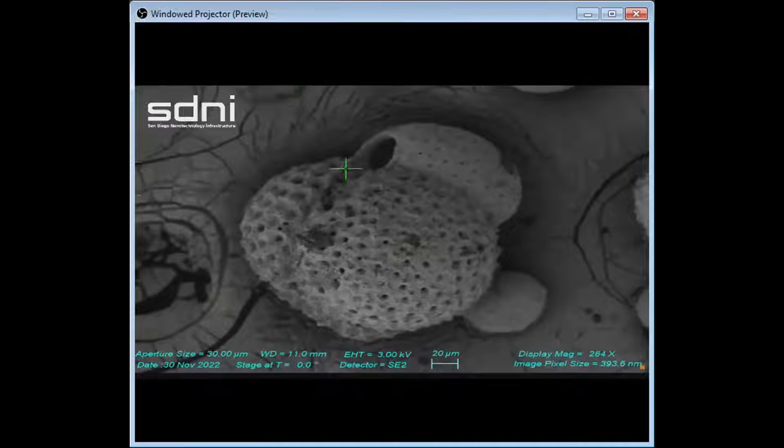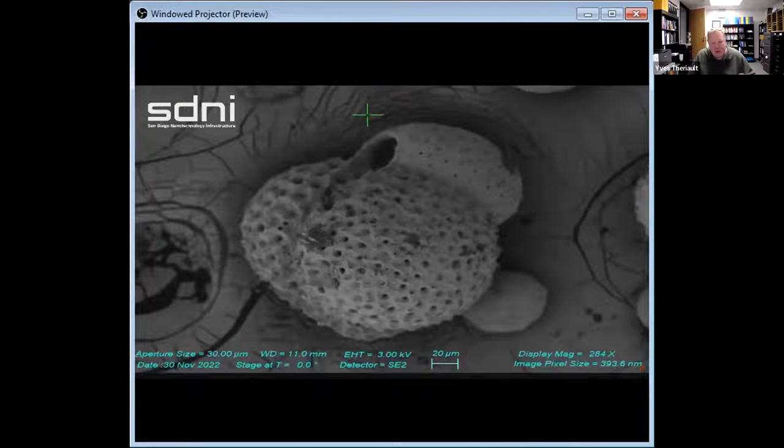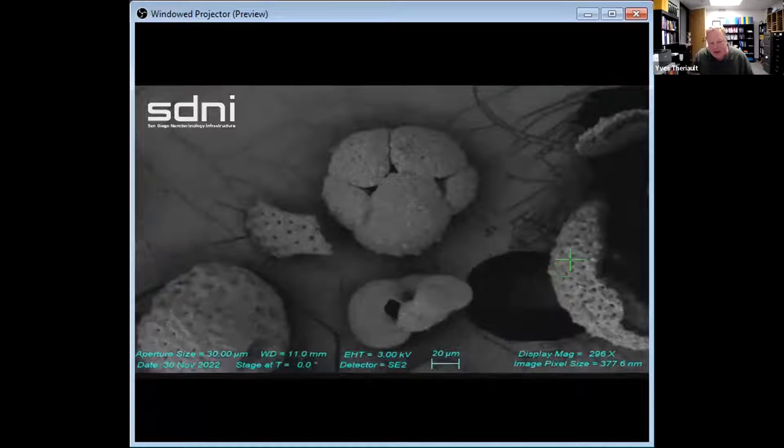When you guys are operating the SEM, you will have control of the magnification and the focus. So what we usually like to do first is start at a low magnification, very zoomed out, and then you focus at that low magnification, and then you slowly zoom in so it's just a little bit out of focus, and then you focus. We know that the controls might be a little bit difficult to use, but we're here to support you as you do it. Also, because the reaction time is kind of slow, we put the SEM, when you control it, in the fast scan mode.